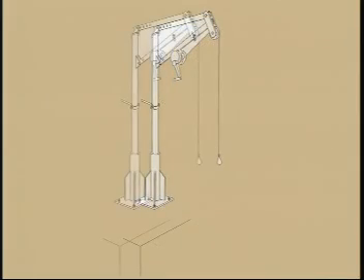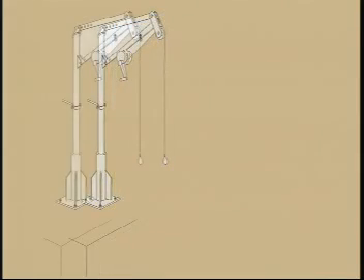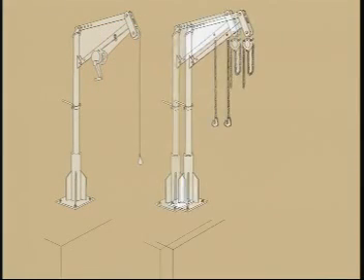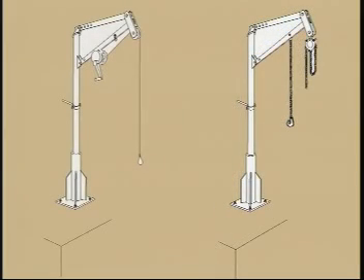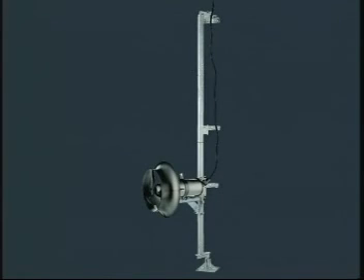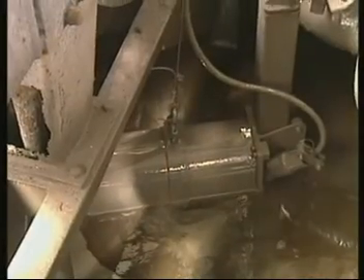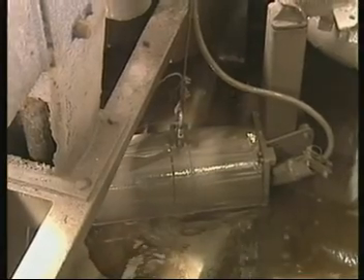To support your installation, Flygt can provide suitable lifting equipment such as lifting davits, winches, blocks, tackles, and chains. We can cover a wide range of different weights. The mixer can be installed on the guide bar in a horizontal position or with a standard angle of plus or minus 10 degrees or plus or minus 20 degrees. Check that the mixer travels up and down the guide bar easily before lowering the mixer to the required working depth.